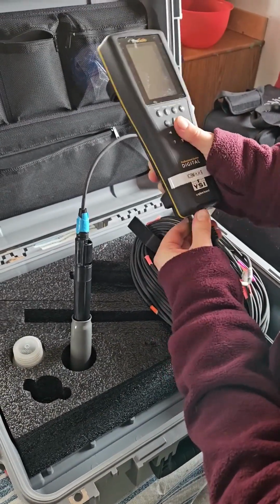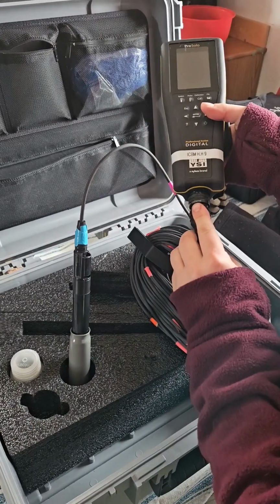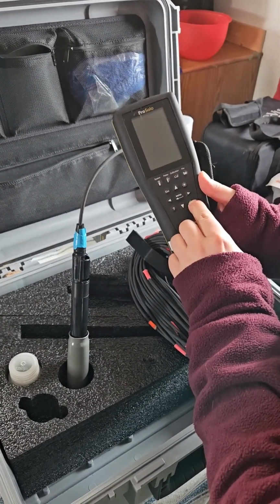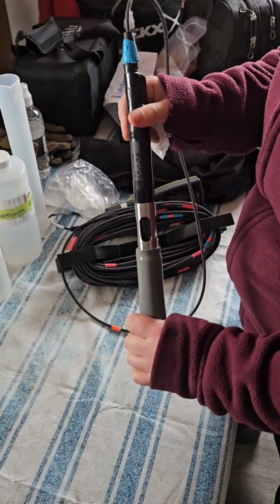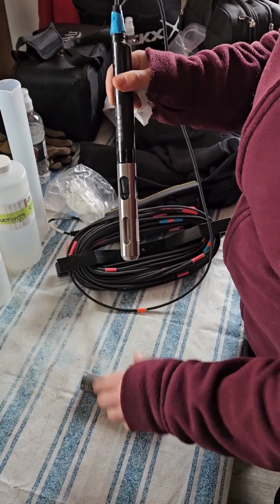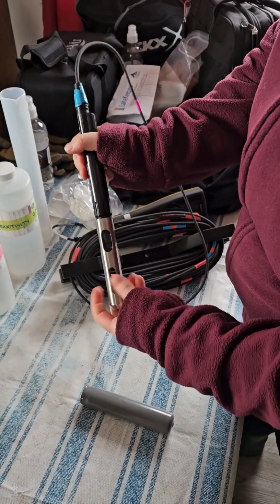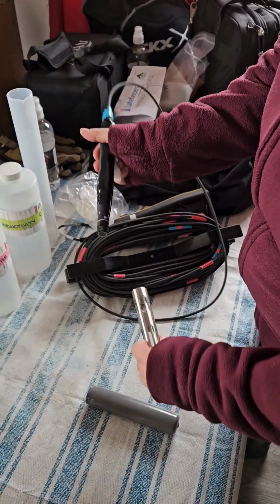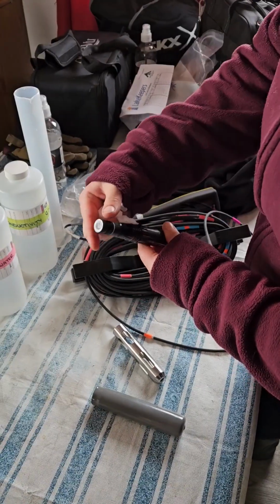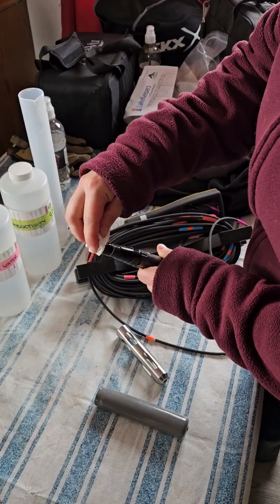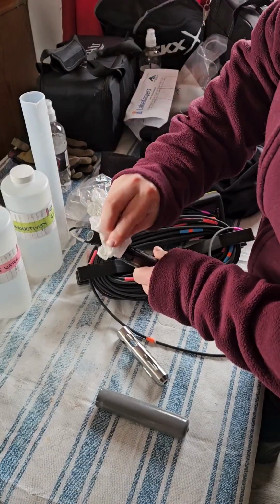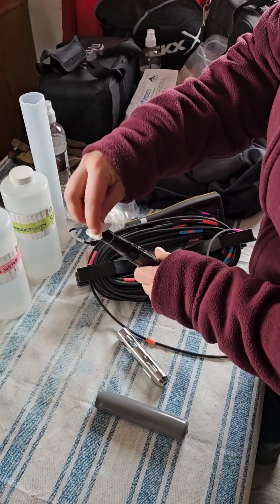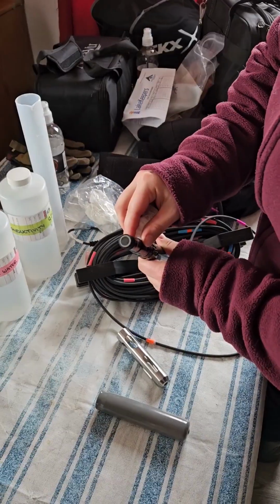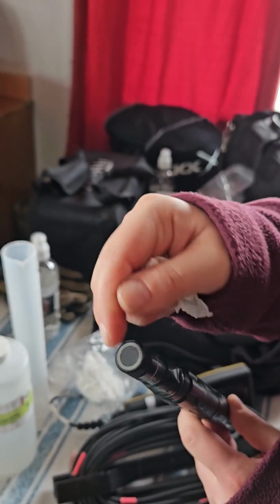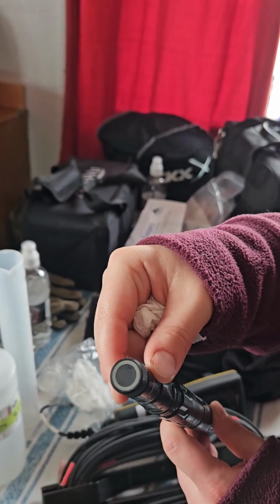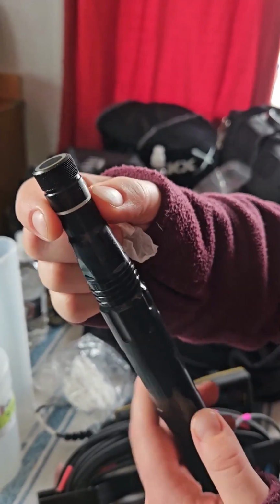We'll start by attaching the probe cord to the handheld and turning on the handheld, removing the gray sleeve and then the metal covering. Be careful when you are removing it that you don't nick the end of the probe or hit the sensors. And we will take a Kim-Wipe that's in your kit and dab the probe tip on and around, just making sure there's no moisture. And then we will inspect the probe sensor to make sure that there's no nicks or bumps or anything like that.